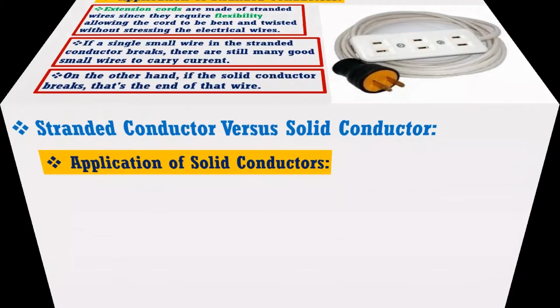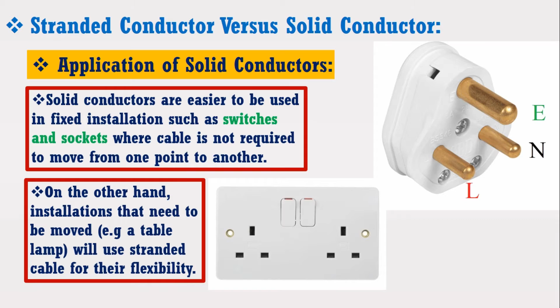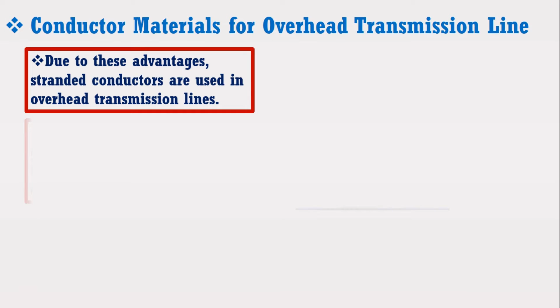Due to these reasons, solid conductors are easier to use in fixed installations, such as switches and sockets as shown in the figure, where the cable is not required to move from one point to another. On the other hand, installations that need to be moved, such as a table lamp, will use stranded cable for their flexibility. Due to these advantages, stranded conductors are used in overhead transmission lines.